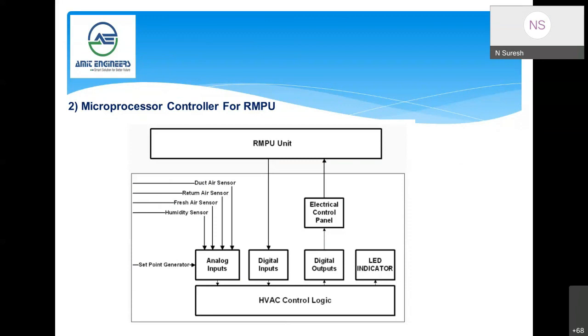The microprocessor is also fixed inside the electric switch panel. This controller is integrated with all the analog inputs, that is, the return air, supply air and fresh air sensors and the humidity sensors. Other than this, there are a few pressure transducers to monitor the system pressure and operate the fans accordingly, as well as give a fault signal in case of any abnormality.